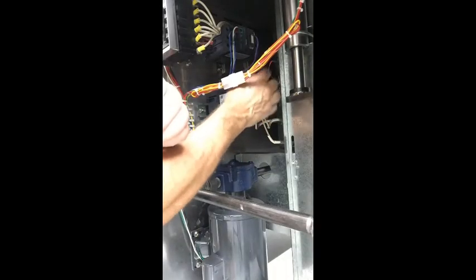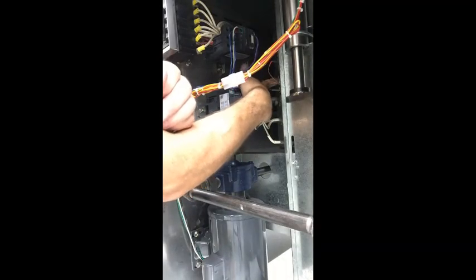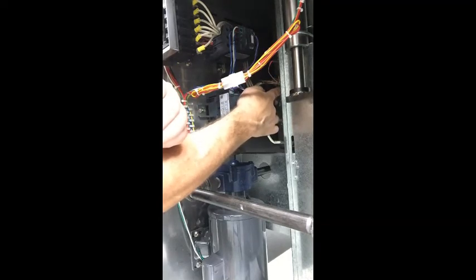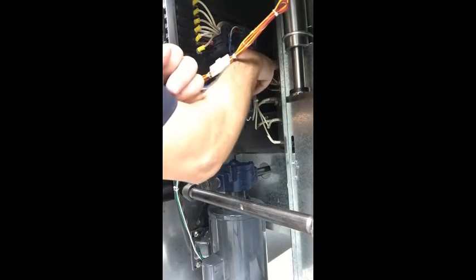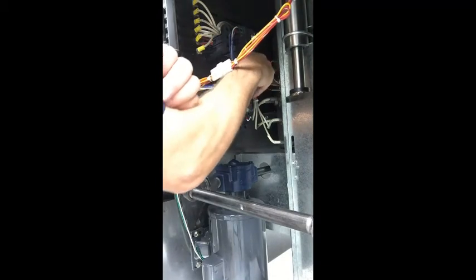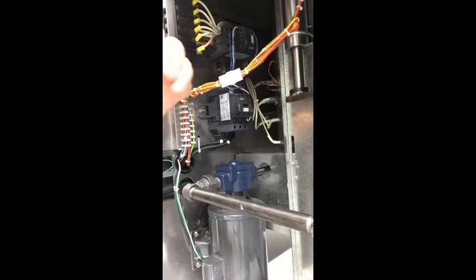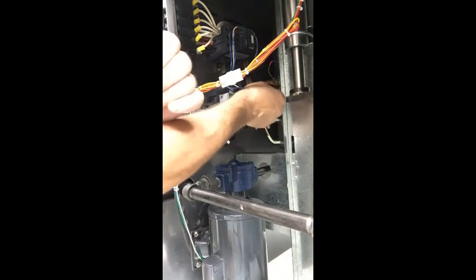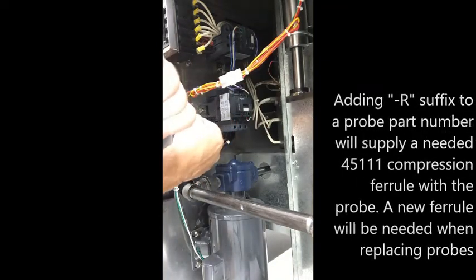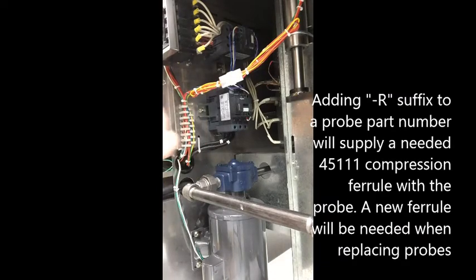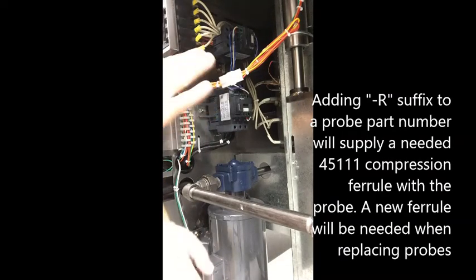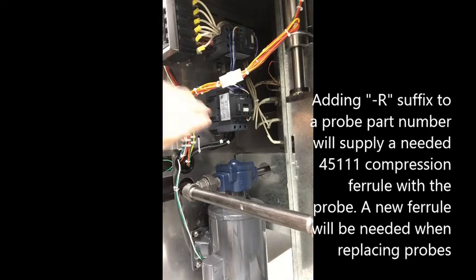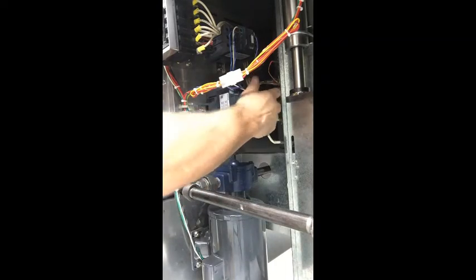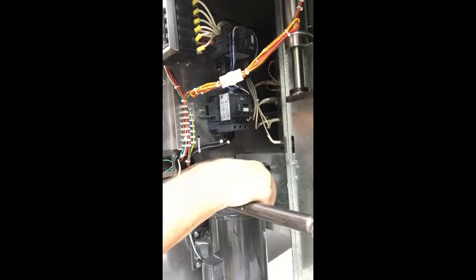Right here, here's your high limit probe. There's your variable probe down below that. And then right up here at the top, right next to where you can still see the add mark, even on this side, you'll find that add level probe. So all of those, just undo the ferrule and you can pull the probe right out the back. When you order a new probe, always add a -R suffix, and that'll get you the little 45111 compression ferrule that you'll need to replace it. You'll reuse that nut, slide it back in, snug her back up, and you're good to go.